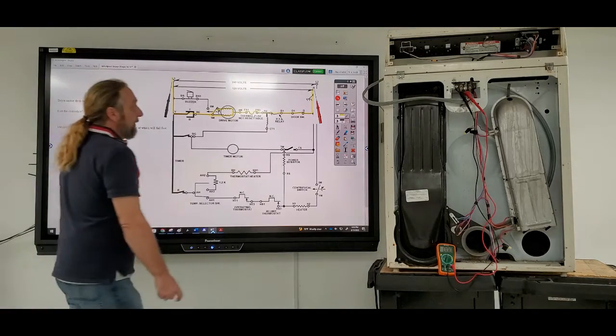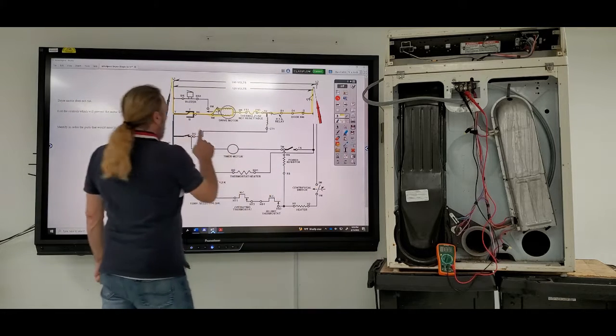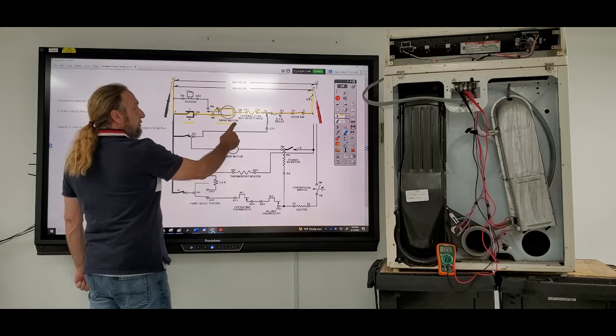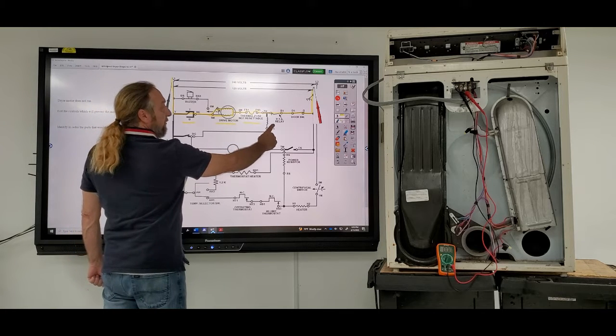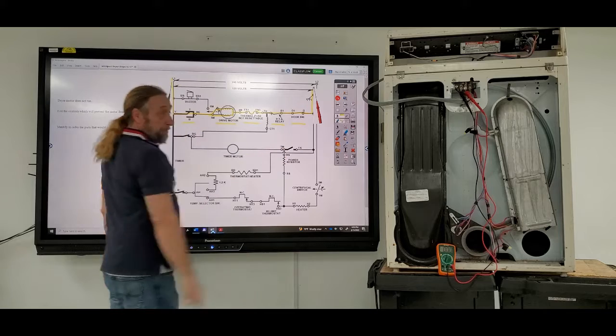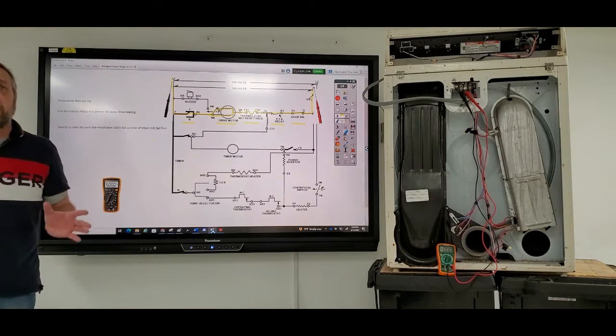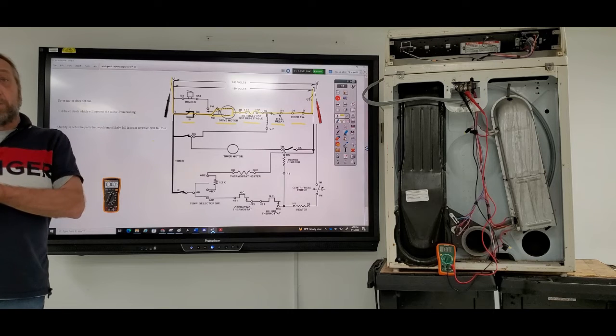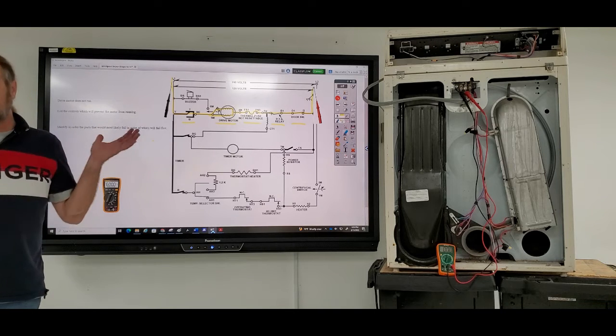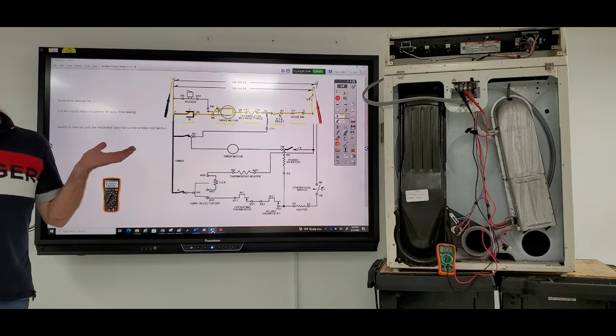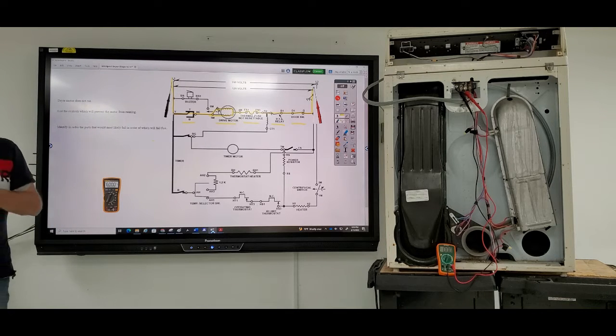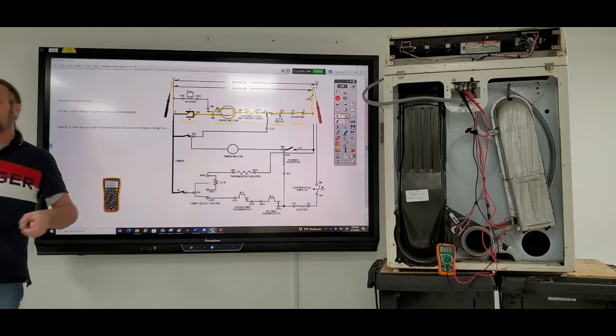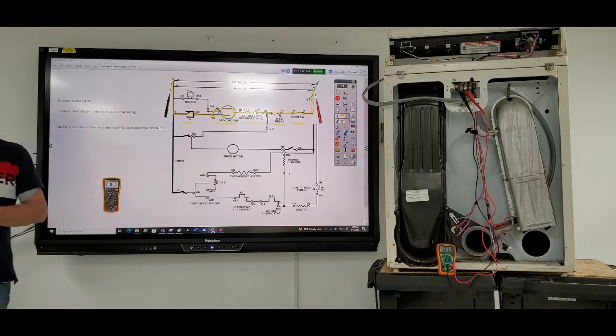So then what we want to do is identify all the components, which are this timer switch, this drive motor, thermal fuse, push to start relay, and door switch. Would the drive motor be a control also? Well, the drive motor's a load. If the drive motor's bad, will the motor run? No. So it's not listed as a control, but it is something in that circuit we have to check. I know I put here list the controls, but the load is also something we need to look at. I was asking for controls because when we start testing, it'll make sense what I'm trying to say.